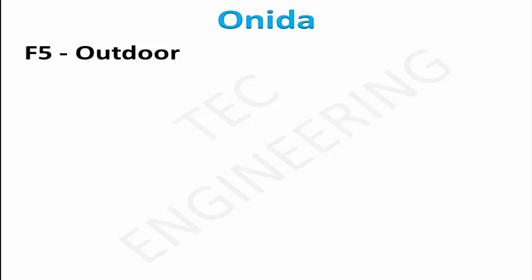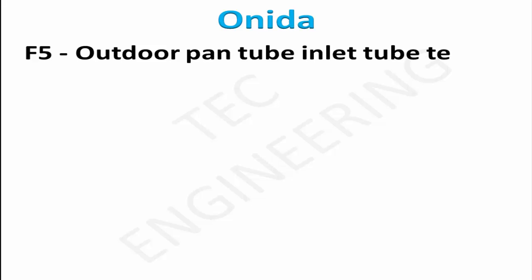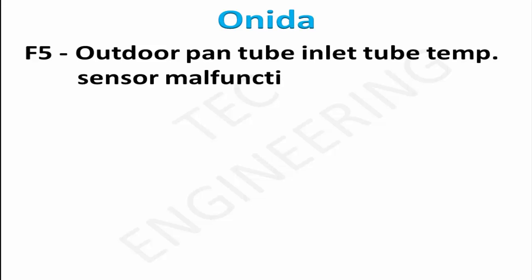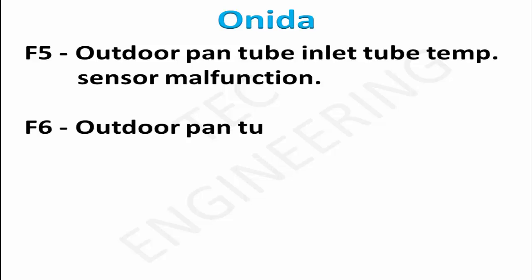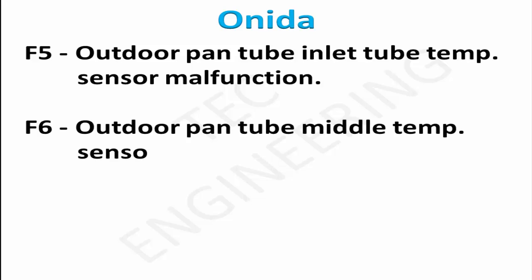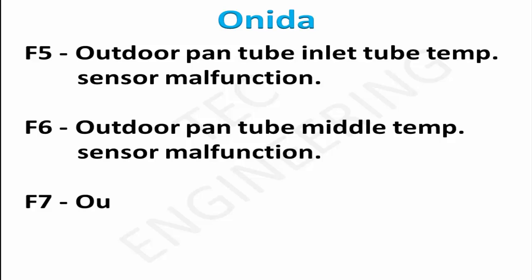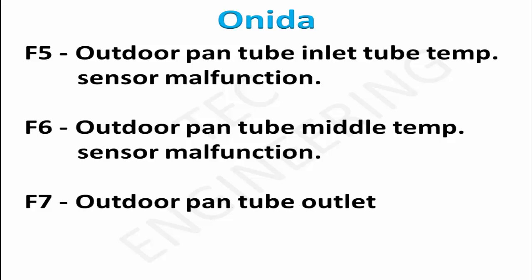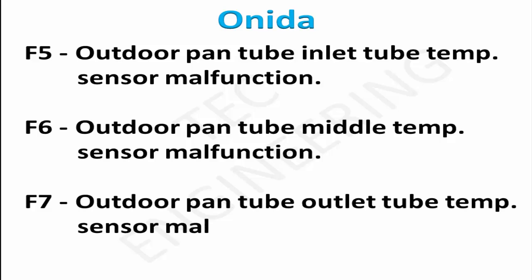F5: Outdoor Pan Tube Inlet Tube Temp Sensor Malfunction. F6: Outdoor Pan Tube Middle Temp Sensor Malfunction. F7: Outdoor Pan Tube Outlet Tube Temp Sensor Malfunction.